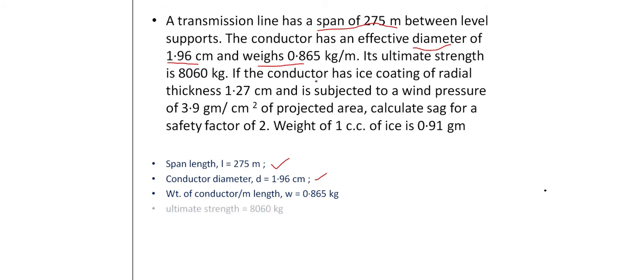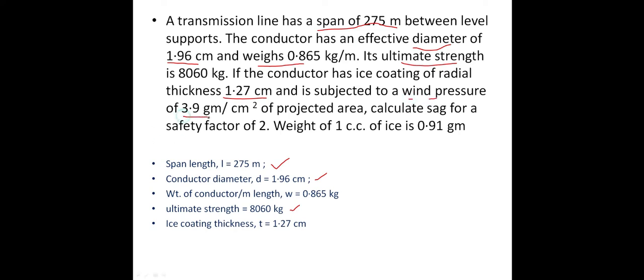If the tension is very low, SAG increases. The conductor has ice coating of radial thickness of 1.27 cm, and wind pressure of 3.9 grams per centimeter square of projected area. Wind pressure and weight of ice are not given directly — only ice coating thickness is given. We have to find ice weight and wind pressure. The safety factor is also given.